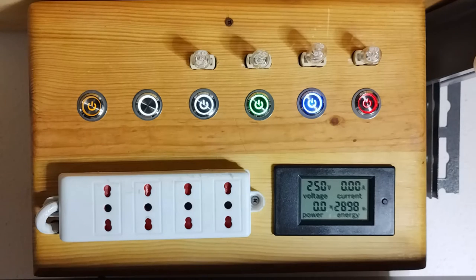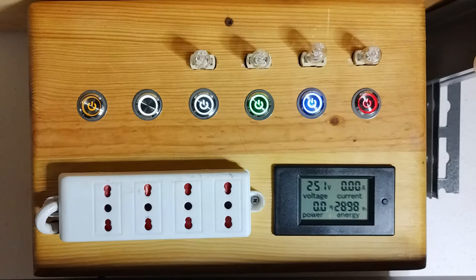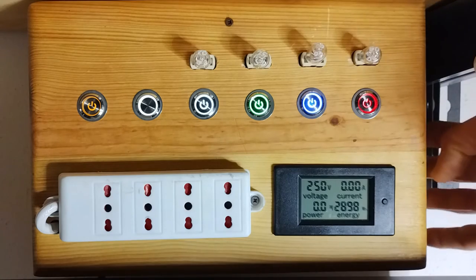All the restrictions are bypassed, turning on the switch hiding on the side of the box. It is clearly visible that the output voltage provided by the isolation transformer is higher than it should be. It reaches 250 volts instead of 230. Under the circumstances, very likely it will never be necessary to use the bypass switch on the side.